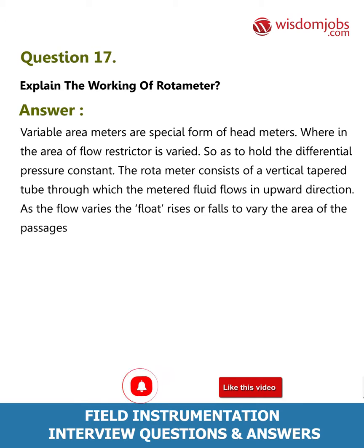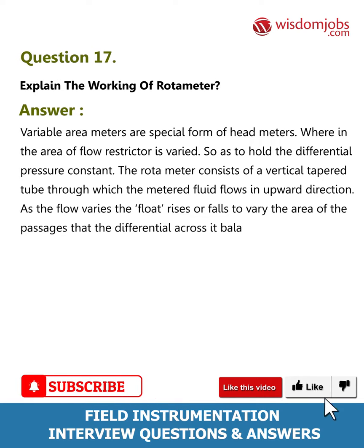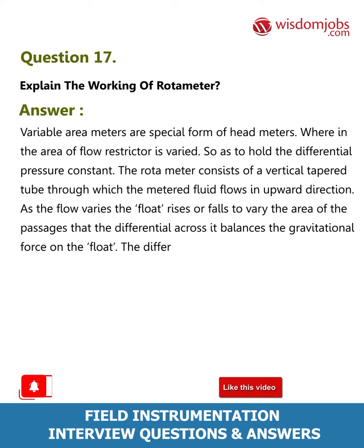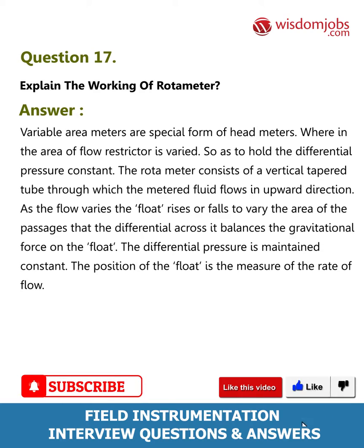The area of the passages varies such that the differential across it balances the gravitational force on the float. The differential pressure is maintained constant, and the position of the float is the measure of the rate of flow.